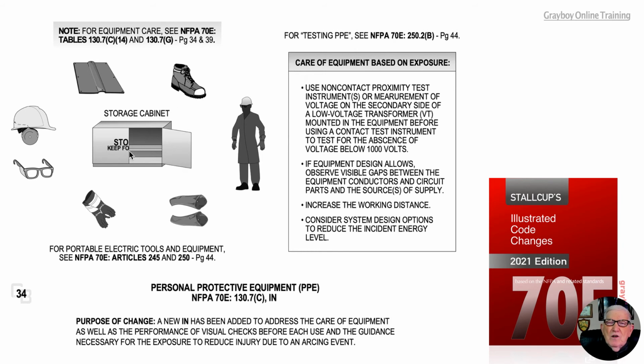Now, as you can see in the illustration, we should have some area where we would store this equipment to protect it from sunlight, fluorescent lights, any type of lighting or condition that could deteriorate its capability to withstand an electrical arc that produces a certain amount of energy without having an effect on the body that would cause a burn beyond a second degree burn, 1.2 calories per centimeter squared. Now notice for electrical tools and equipment, 70E refers us to 245 and 250 on page 44 of the NEC.